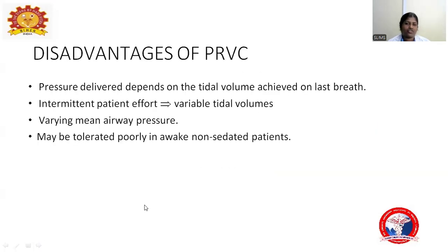So what are the disadvantages of pressure regulated volume control? The pressure delivered depends on the tidal volume achieved on the last breath. So for every breath the ventilator provides the pressure, and that will be determined on the last breath that the patient has taken. The second disadvantage is intermittent patient effort.